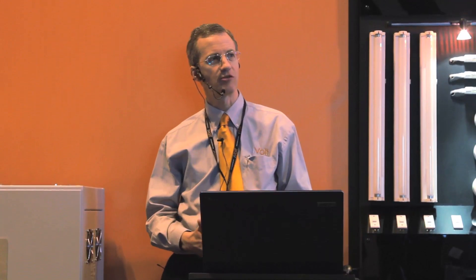What is voltage optimization and how does the iVolt work? In the UK, electricity is supplied generally to sites at 240 volts — the typical average is about 242. But a lot of the equipment on site will quite happily work at a lower voltage, and in fact was designed to work at a lower voltage, particularly with European legislation. By supplying it with higher voltage you're very often using more electricity, higher wattage consumption, which apart from costing you more also heats the equipment. Lamp temperatures are higher, motor temperatures are higher, and this actually reduces the lifetime of the equipment. So voltage optimization aims to reduce that voltage down to the correct optimized voltage level, prolonging the life of the equipment and reducing the electricity bill in the process.